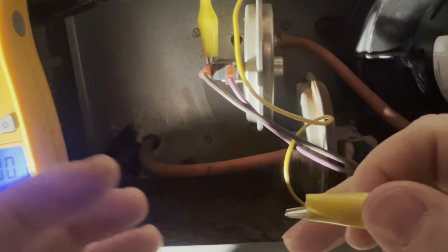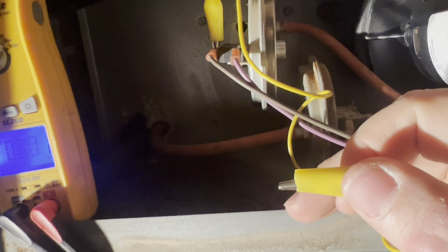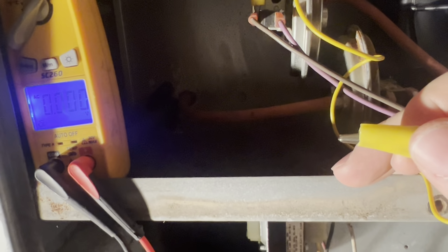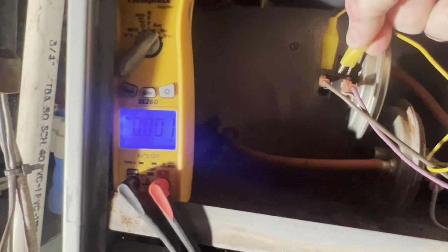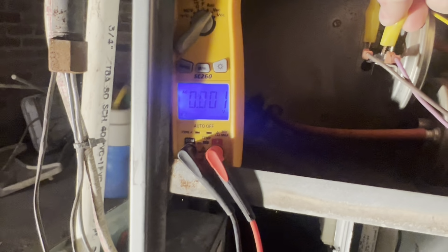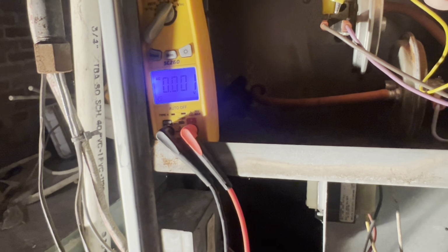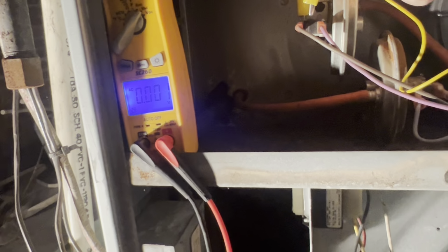So I'm going to show you guys how to bypass a pressure switch. When the unit starts, it wants to see this switch open. It does not want to see it closed. If it's closed, it's a problem. So what we're going to do is bypass this pressure switch and allow the unit to turn on, because we know that this is bad. So you need to put your alligator clips on one side, get your alligator clip to go on the other side. Just get ready for it, right? Not yet. So what we're going to do is hold this down to start the unit, let the unit run and think that the switch is in fact open, and then we're going to put the jumper on and close it.